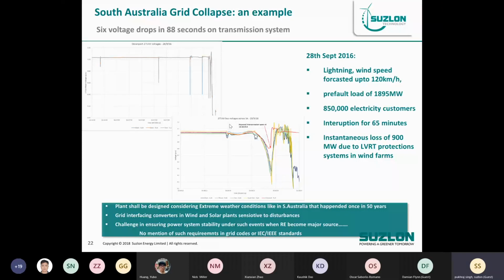What happened with such a repetitive LVRT event was that this was never thought possible. We always think one LVRT event comes and then it's over, and maybe the next comes after some months or hours, but not within 2 minutes. This led to the tripping of wind farms. Some wind farms could withstand 2, 3, or 5, but nobody had programmed the turbine to withstand 6 or more in less than 2 minutes, because it's a highly unstable grid.